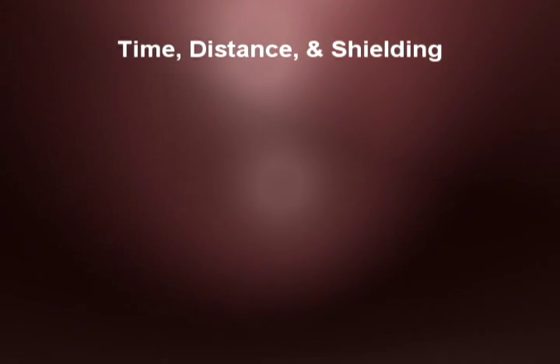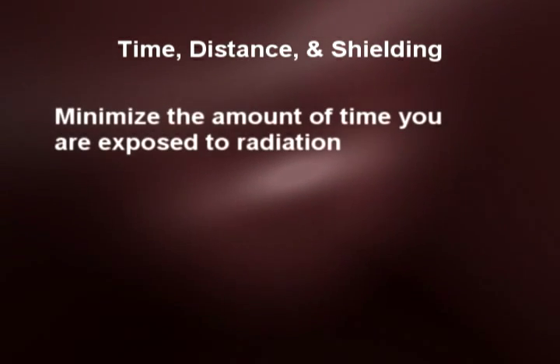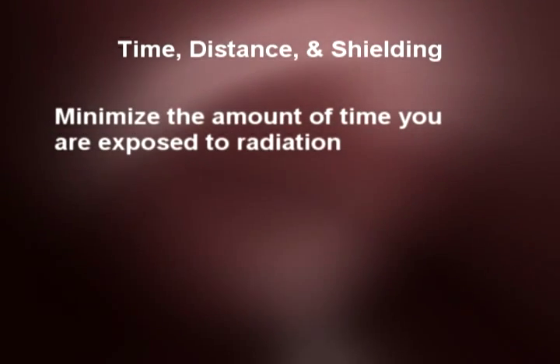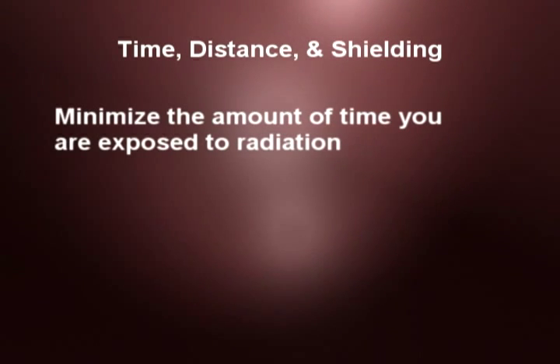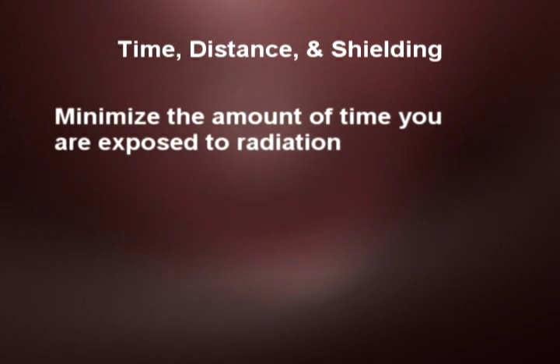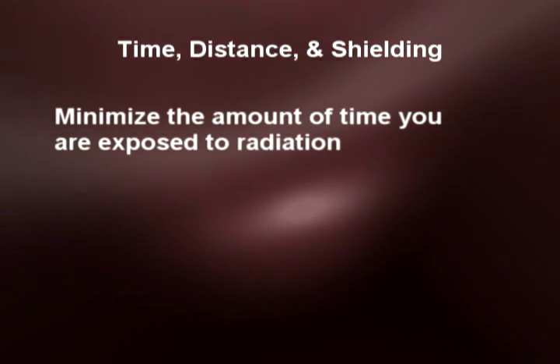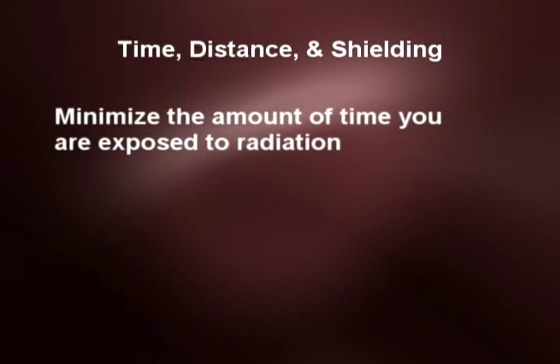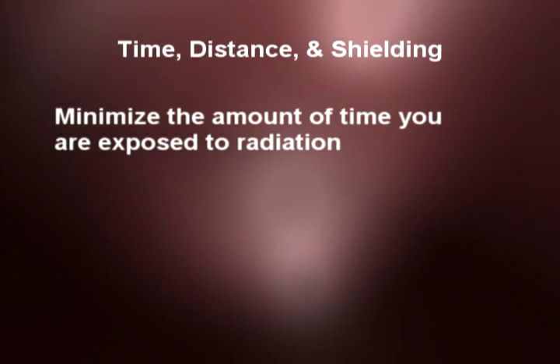With any X-ray source, whether it's a hospital machine or an industrial machine, there are three basic principles of radiation safety: time, distance, and shielding. You should try to minimize the amount of time that you're exposed to the radiation, be out of the room when the radiation device is on, or at least minimize the amount of time that the device is on when you're in the same room. If you minimize the amount of time that you're exposed to the radiation, your dose is going to be lower.